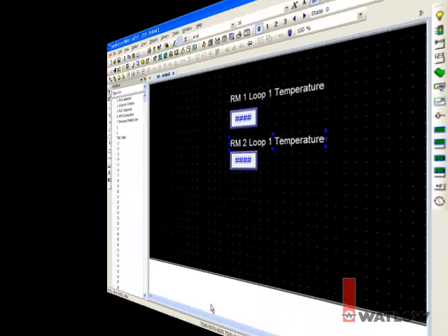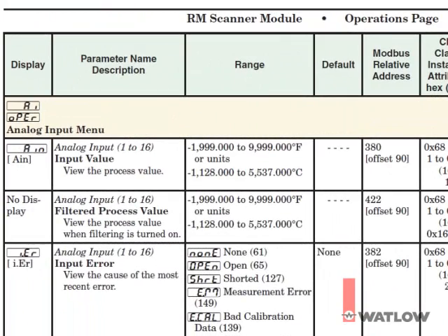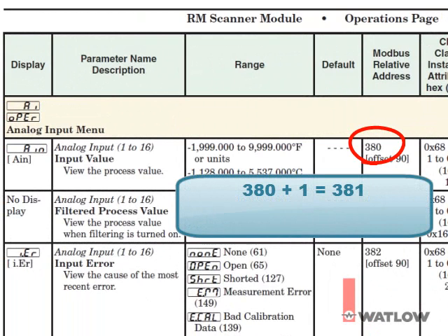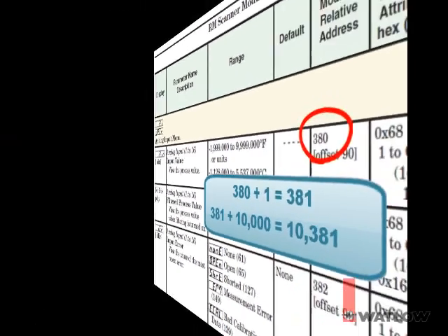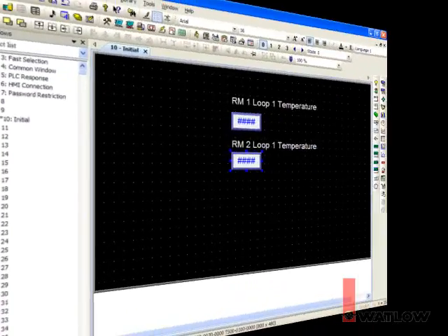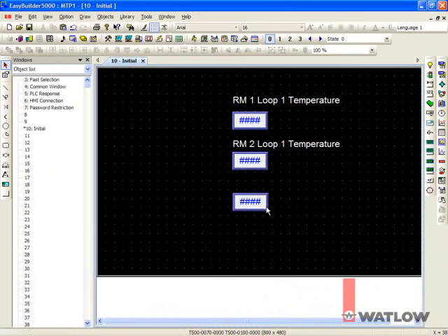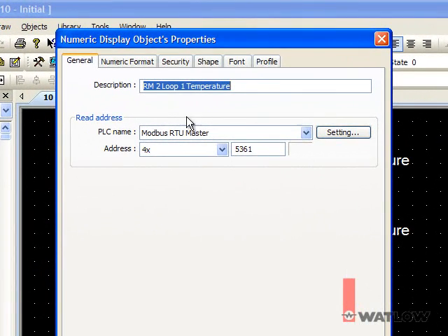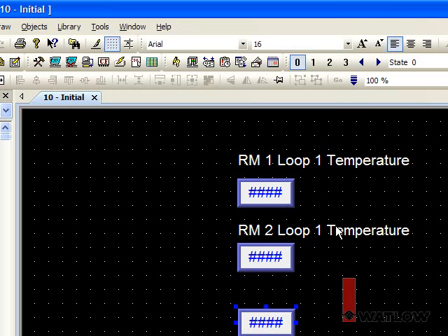To access the first analog input value in the scanner, consult the manual and find the Modbus address is 380. To that, we have to add 1 to use it with the OIT, and add 10,000, because that's the offset for the scanner module we entered in the gateway. So the address is 10,381. Again, copy, paste, deselect, and edit. Select it, and add a label.